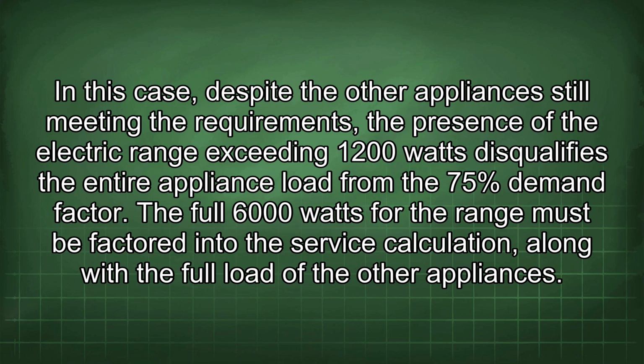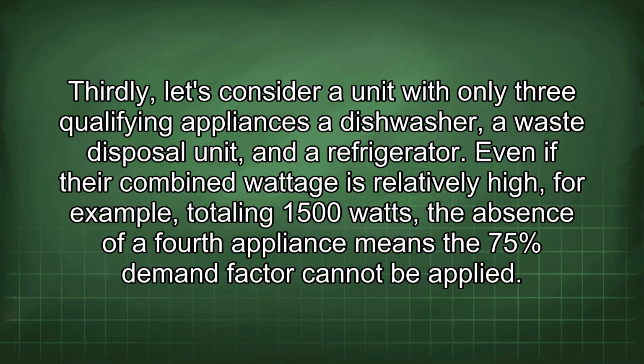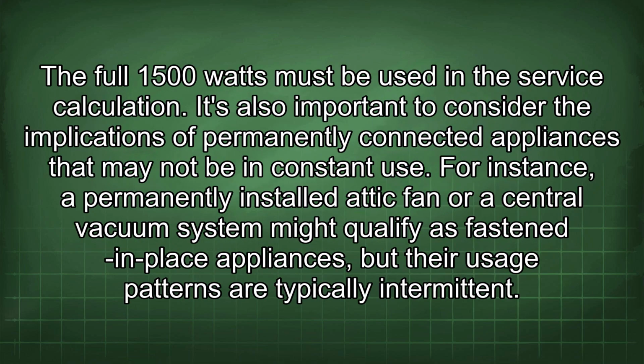Thirdly, let's consider a unit with only 3 qualifying appliances: a dishwasher, a waste disposal unit, and a refrigerator. Even if their combined wattage is relatively high, for example, totaling 1500 watts, the absence of a fourth appliance means the 75% demand factor cannot be applied. The full 1500 watts must be used in the service calculation.